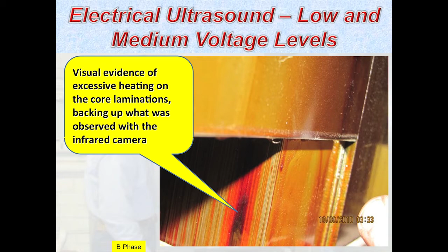That's a darkened area, and these are all pieces of iron that are laminated and bonded together. I don't know if anybody knows how a core is put together, but it's a whole bunch of pieces of iron that are laminated, bonded together, varnished and baked. That varnish is a pretty nice finish when it's on there. You have clamping bolts that go through to hold it together nice and tight, and those laminates make sure the flux lines are concentrated properly.